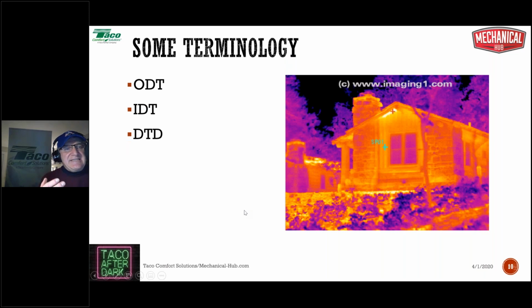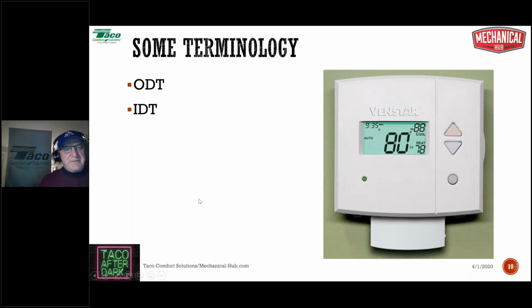And then there's DTD - design temperature difference. It's simply IDT minus ODT. Your indoor design temperature minus the outdoor design temperature gives you the design temperature difference. It's the difference between what you want indoors on that quote-unquote coldest day of the year outdoors. What DTD will become is a multiplier, which you will see.